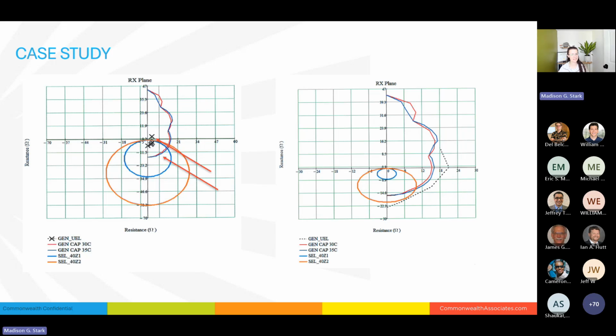Quick case study. This is the same example from before, where we see kind of the exact inverse of the power graph. And here we have our under excitation limiters way on the inside, unfortunately not protecting anything. For the impedance plane, you work from the outside in. So you start all the way out here. What do we hit first? Zone 2 relay, zone 1 relay. Oh my goodness, instantaneous trip. And then we hit our reactive power capabilities. And then we hit our limiter all the way in here. And that's really not what we want to see.